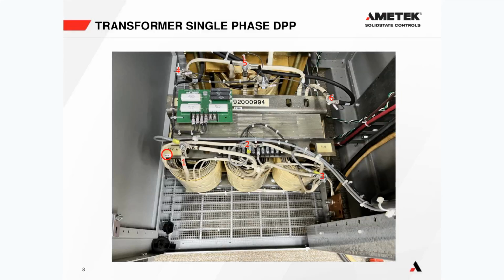And then on the top side is the secondary, terminals 4, 5, and 6. Okay, and that is the secondary side of the transformer. And on that side, depending on what your DC bus is, if it's a standard 60 cell valve regulated or lead acid battery, then you're going to get around about 130 volts phase to phase on the secondary of the transformer.